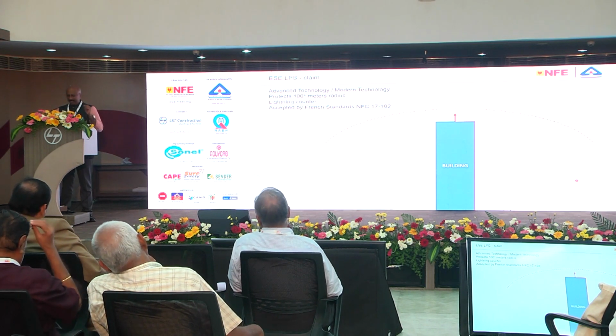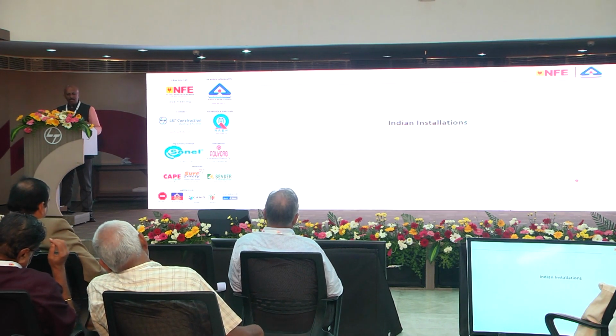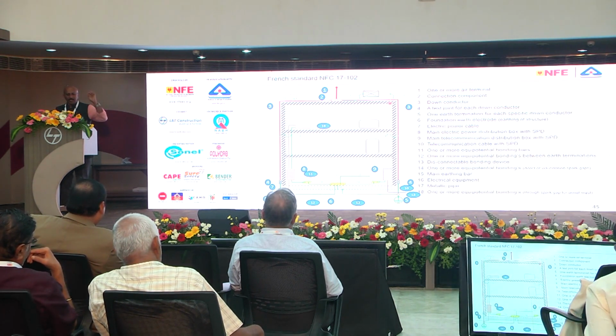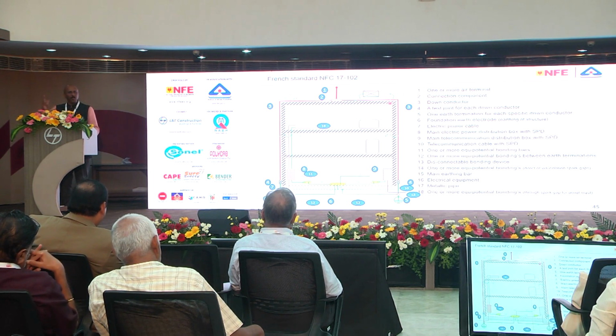That is the problem. Now, how the French code is made, you can see in this picture from the French code. In the French code, you leave the item number 1. Item number 1 is the air termination, the ESE rod. The serial numbers 2 to 18 are nothing but our Indian lightning protection, the conventional IEC 62305. So what the French code says is, indirectly, you make a Pakka lightning protection system, and over and above you put a rod. Now this rod is protecting you and 100 meters all around.